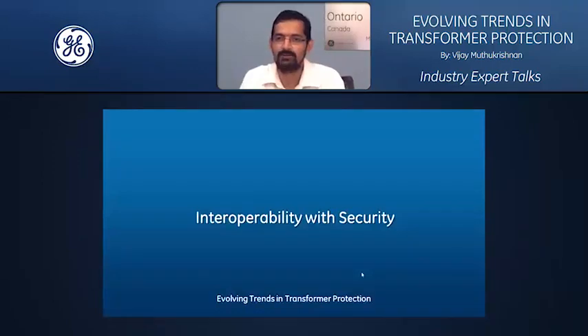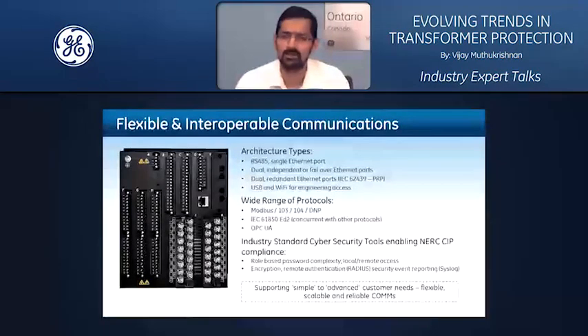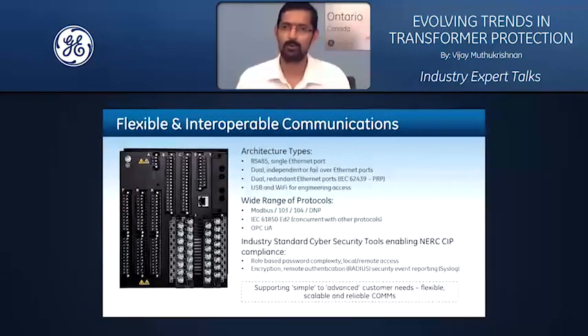Now that we have covered a variety of protection, control, and logic functionalities that are part of a transformer protection relay, let's look at the communication, networking, and cybersecurity front of what a transformer protection relay can offer. The real need here is that you want to be able to connect to your transformer protection relay, pull information, and deploy control commands through the communication network.